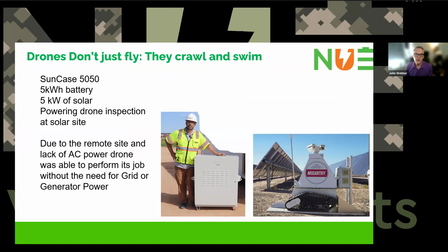The example here was a drone charging station we used with our larger unit. That's a 5050, a 5,000 watt inverter that can take up to 5,000 watts of solar, and a 5 kilowatt hour battery. But because we have external ports, we can add another 15 kilowatt hours of batteries. We could have a 20 kilowatt hour system ready to go inside two of those boxes that Zach, one of our employees, is standing next to.